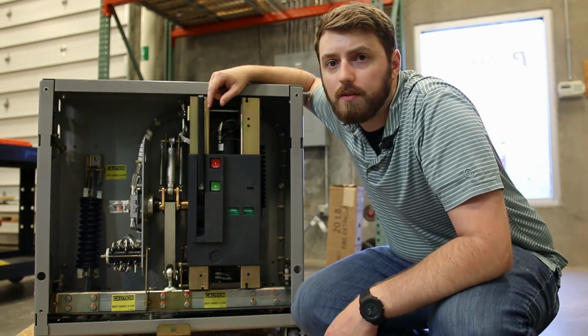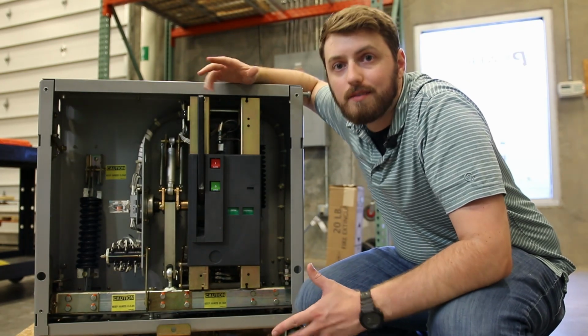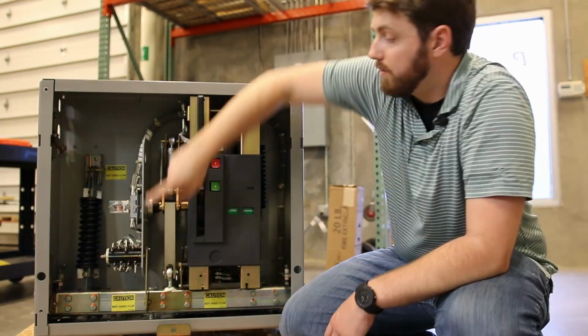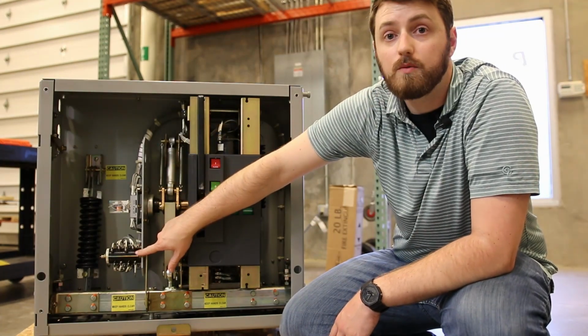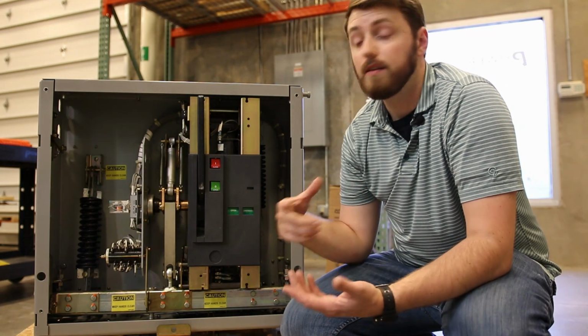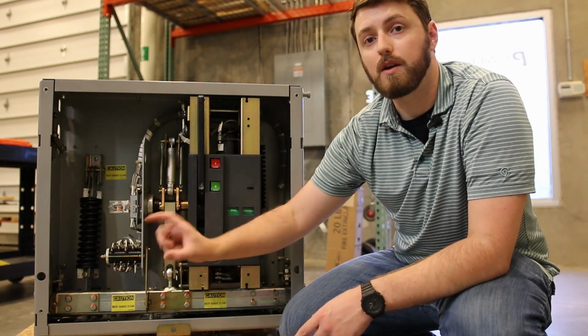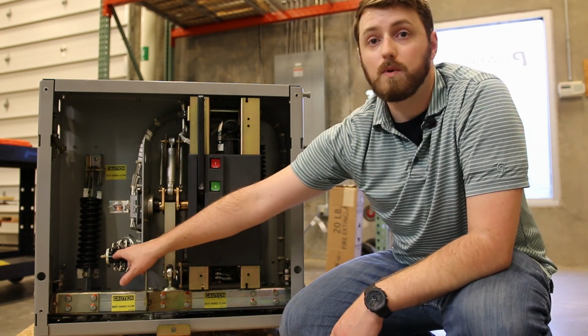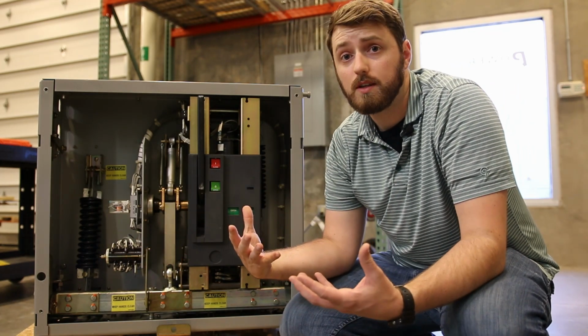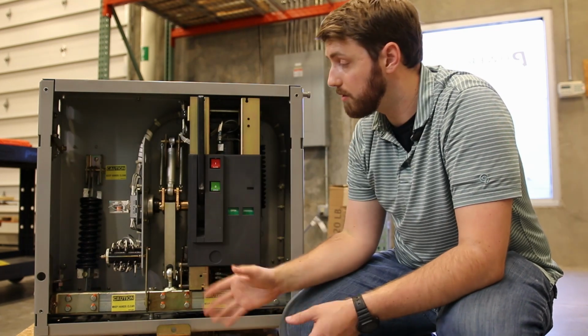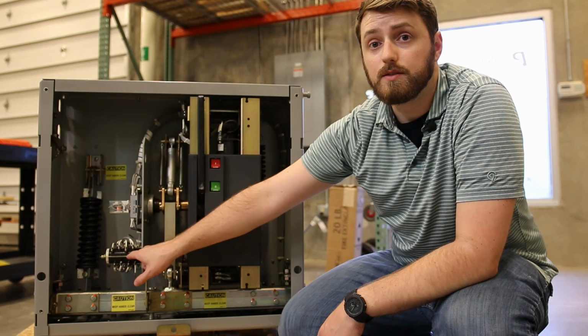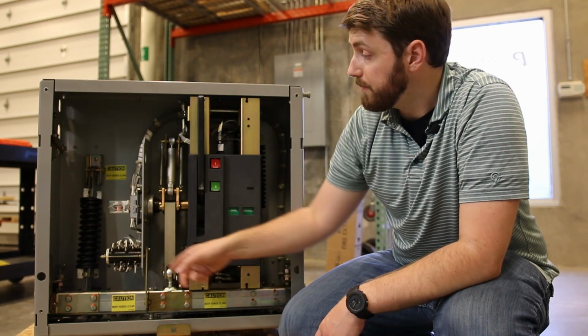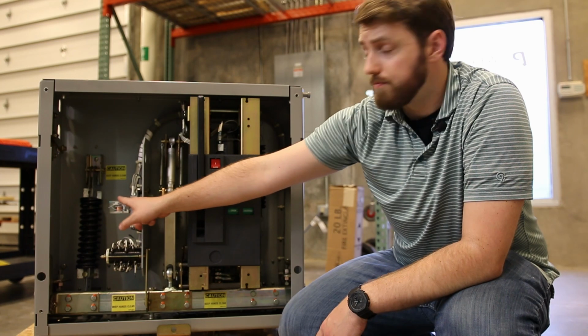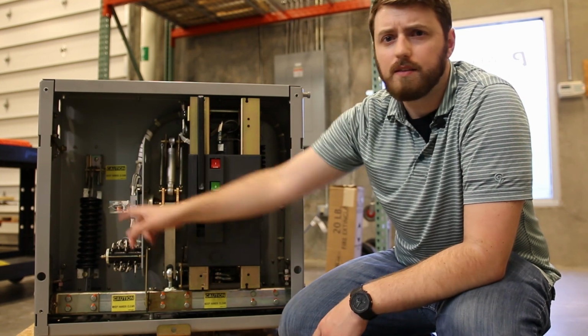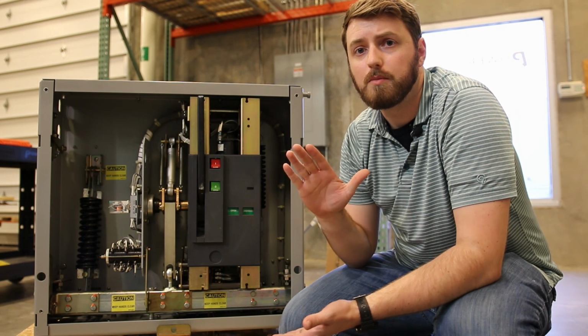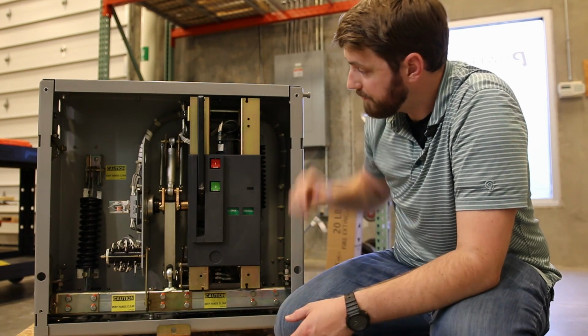One thing you'll notice as we look around inside here, there's not really any electrical controls. There's a couple. We've got some aux contact switches in here, which connect to the secondaries on the back, that this physical thing rotates when this main operate rod rocks back and forth. This is what tells the external control circuits out in the cell or in the switchgear whether the breaker is open or closed. This is our Y relay. Some breakers call it the anti-pump relay. This is what prevents the breaker from going open, close, open, close over and over again.